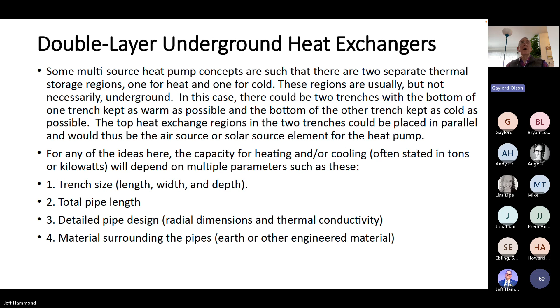This shows a modified slinky loop trench. Instead of having only one slinky loop at the bottom of the trench trying to get stable temperature, we're going to have two slinky loops in this same trench, one as close as possible to the surface and the other at the bottom. The slinky loop at the top of the trench will function as a quasi air-to-liquid heat exchanger and as a partial solar thermal collector.